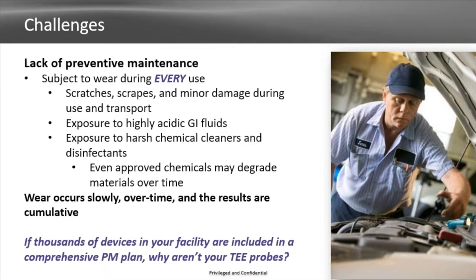And exposure to harsh chemicals and highly acidic gastrointestinal fluids. The chemicals used to disinfect these are highly caustic, and they're there for a reason, because we need to make sure these are disinfected, since the vast majority of the time these probes are not used with a cover. They're used bare and inserted, so they're subjected to whatever pathogens are inside that patient. We want to make sure we do a high level disinfection on these. These cannot be sterilized, unlike some endoscopes. They have to be high level disinfected.